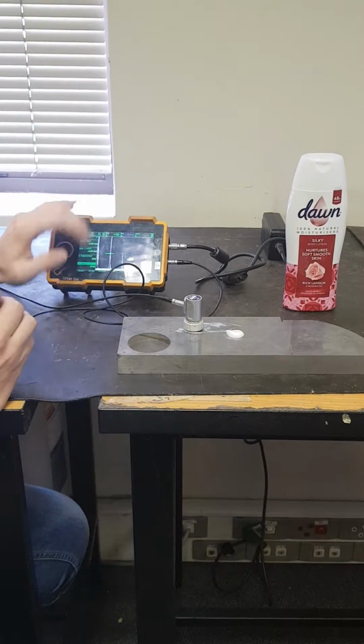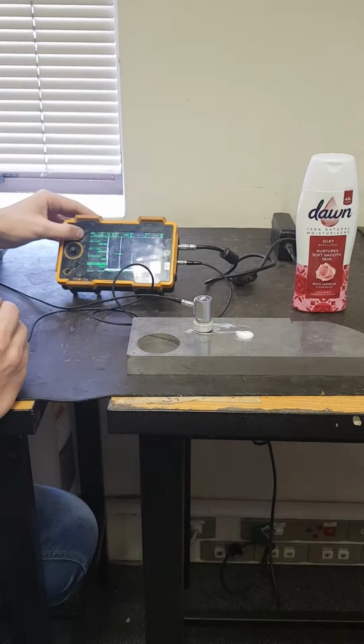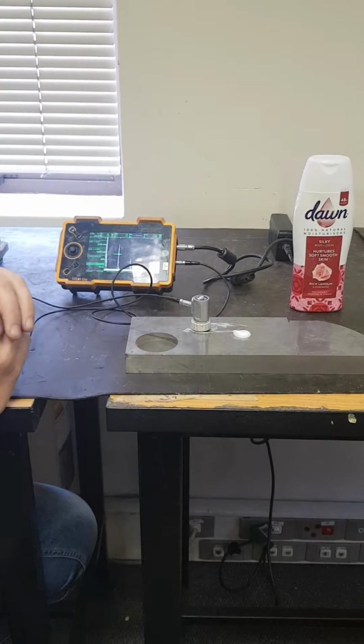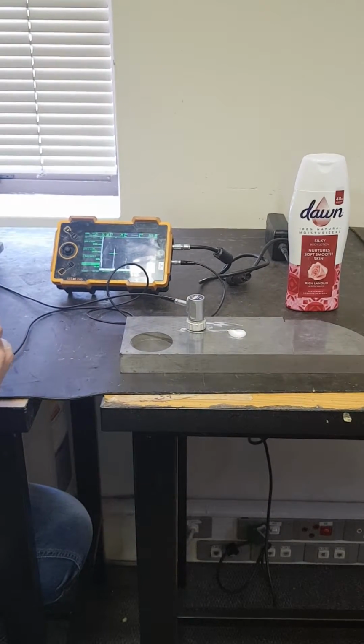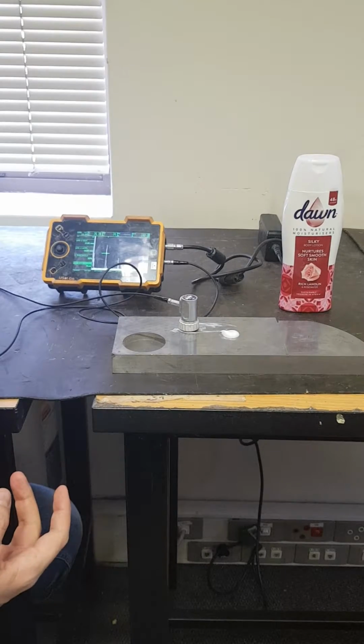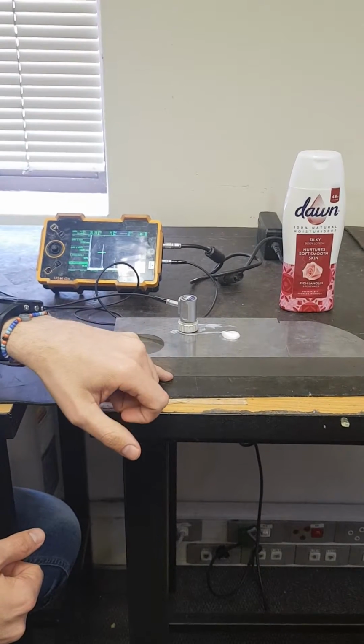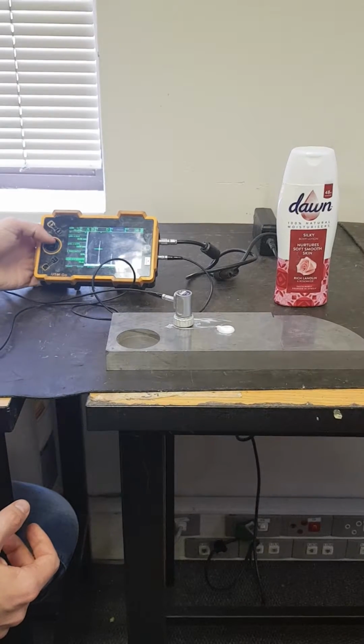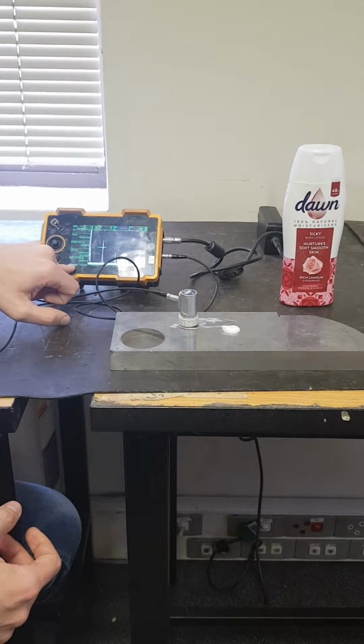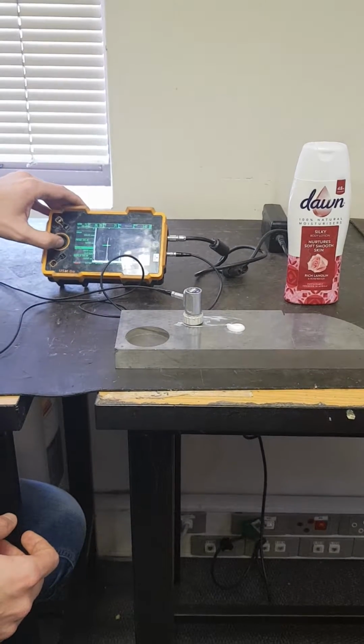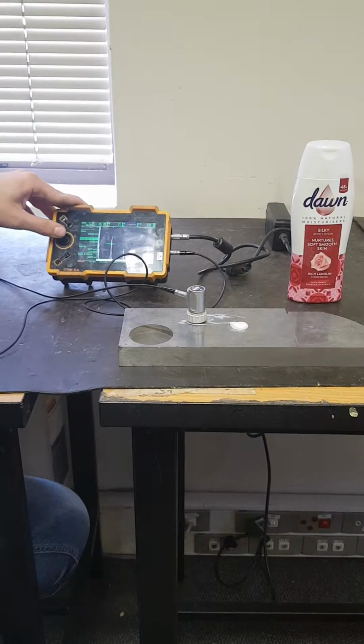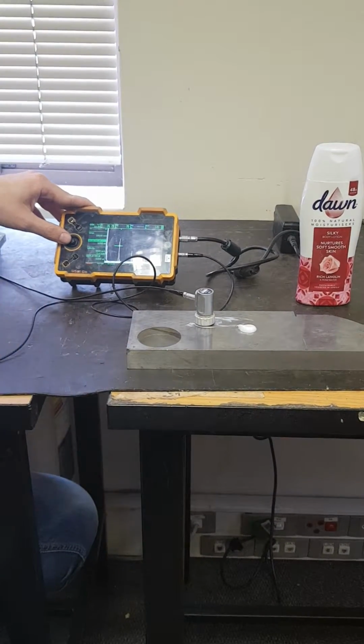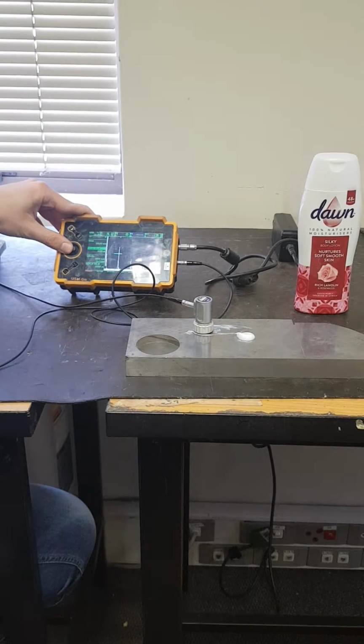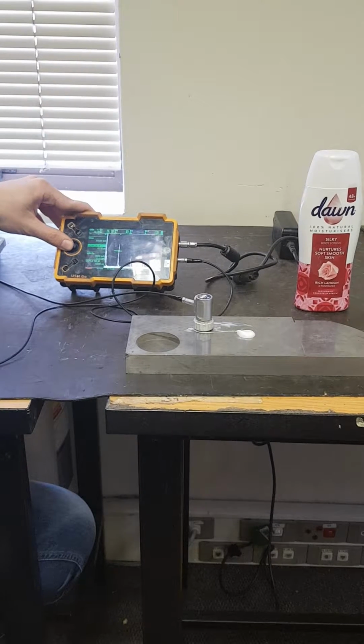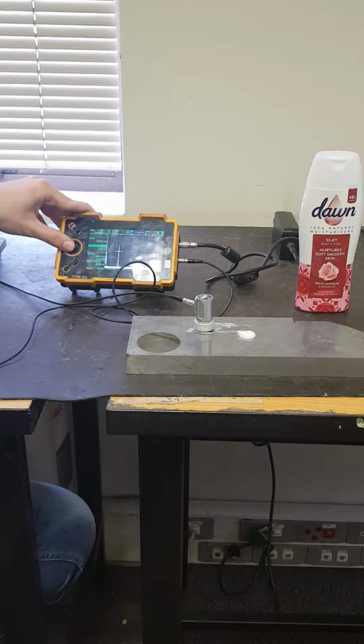Now that peak, you see the first peak there? It's through the roof. So I'll just adjust my decibels so that peak is at roughly 80% of my maximum screen height. The block itself is 25 mils thick. So what you guys do, you go to your range menu and set your probe delay. On some machines this is called your 0 or your probe 0 or your standoff or something like that. In this set it's called the probe delay.